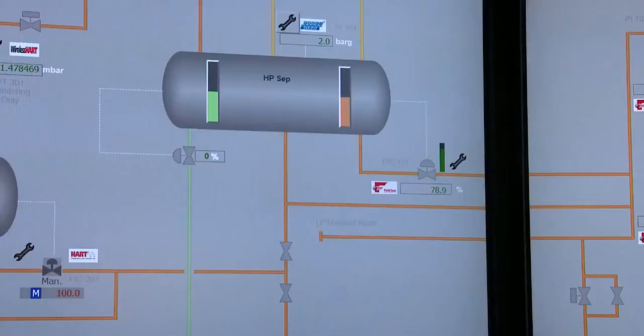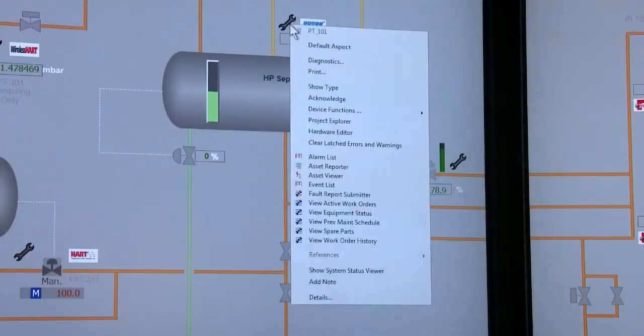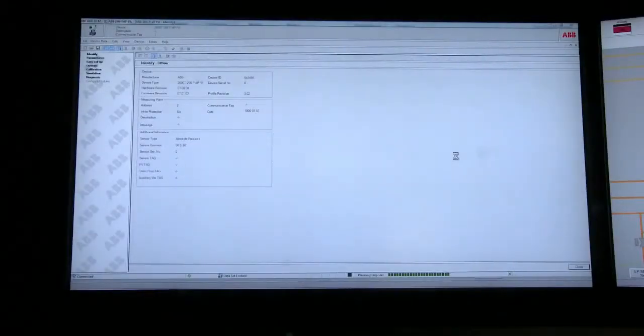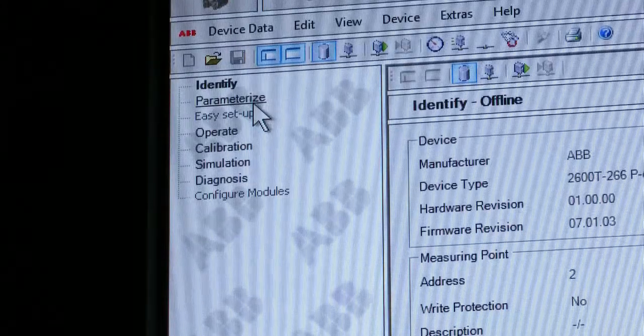With the aspect object technology and the integrated ABB asset management system, from a right-click we're able to get direct access to intelligent data from instrumentation or devices in the field. Here we can access a pressure transmitter, and from the DTM I'm able to get diagnostic or parameterized information directly on the 4 to 20 milliamp signal — the same whether we use Profibus PA, DP, or Foundation Fieldbus.